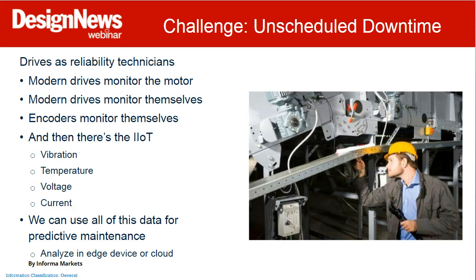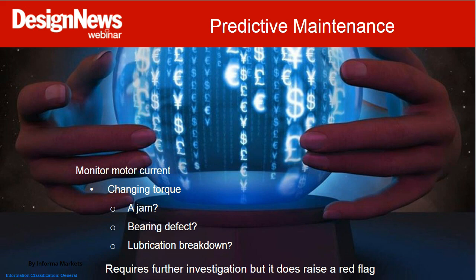So that holds for predictive maintenance, but really just remote maintenance in general, and how it might look for a drive. Torque is a function of current, right? And if your drive gets feedback that your motor shaft or load is not going where it's being ordered, it's going to modify the torque to get the load to the proper place. But something caused that change — it could be a jam, a bearing cage defect developing, or lubrication issues.